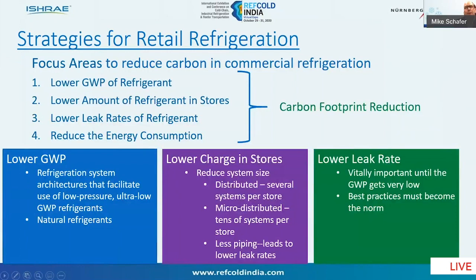We have 4 focus areas when we talk about reducing carbon footprint in commercial refrigeration stores. The first one will be lowering the GWP of the refrigerant, lowering the amount of refrigerant in the stores, and then we'd like to lower the leak rates for refrigerants. And then the other piece that comes into play is reducing energy consumption. And that comes about relative to choosing the most energy efficient system, as well as store design from a merchandising perspective. We've seen a tremendous change in our industry where open cases, whether it's dairy or deli, predominantly have doors on the cases. So that reduces the overall energy requirement by 50 to 60%.